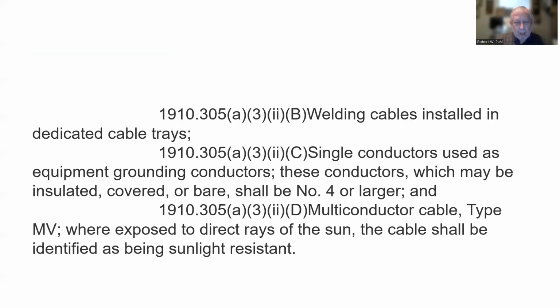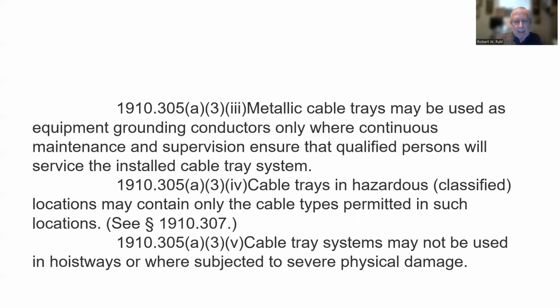Oh, that's the following methods that can be in cable trays. Okay, single conductors used as equipment grounding conductors. Multi-conductor cable type MV. Metallic cable trays may be used as equipment grounding conductors only where continuous maintenance and supervision ensures that qualified persons will service the installed cable tray systems. Cable trays in hazardous classified locations may contain only the cable types permitted in such locations, 1910.307. And cable tray systems may not be used in hoistways or where subjected to severe physical damage.